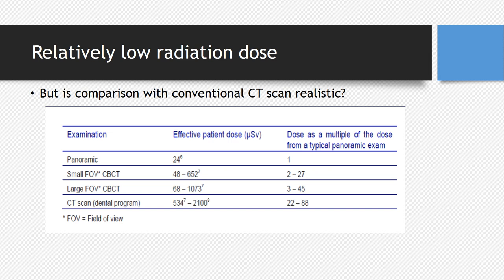Regarding the relatively low radiation dose compared to conventional CT: if a panoramic radiograph dose is taken as 1 (approximately 24 microsieverts), then a small field-of-view CBCT is about 2 to 27 times that of a panoramic radiograph, a larger field-of-view CBCT is about 3 to 45 times, whereas a conventional computed tomography scan utilizes 22 to 88 times that of a panoramic radiograph.